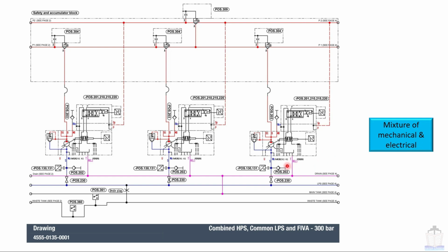Now once again I want you to focus on this point SP. In this configuration you can see that this SP is not connected with the B1 as we saw earlier, but this SP line is connected with this P2, that means the electrical driven HPS pumps outlet manifold. When a combined HPS system is installed on the ship, then in that case this SP point is connected with the P2, not with the B1. Why? Because startup pumps start first, and on the basis of that pressure the rest of the engine driven swash plate pumps function. I hope this is clear.